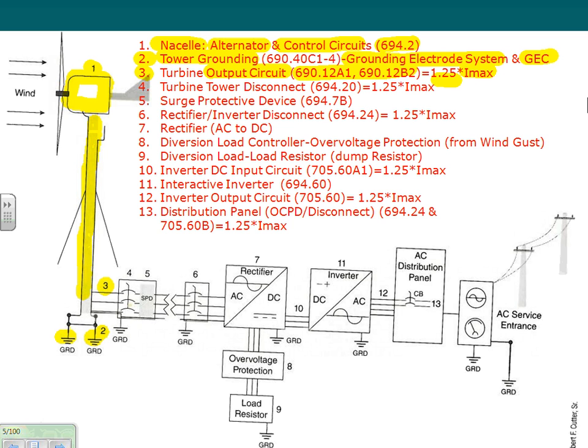And as we all know, guys, we're most likely outdoor, so what do you use? THWN conductor insulation, anything that has wet-rated conductors. And when you go underground, since you're outdoor in a wet location, I always tell my students, being an engineer and mathematician, the wiring method if you're outdoor is PVC conduit. You can use rigid, you can use EMT, but the conduit of choice if you're underground or outdoor is PVC schedule 80 or 40, and you put them underground and pull your conductors. How many conductors do you want? If it's 3-phase, you need to be carrying at least 3 conductors. You have to have an equipment grounding conductor with it, and you have to have a neutral if the turbine has a neutral. So that's what this calculation is all about. Any comments, guys, about this?